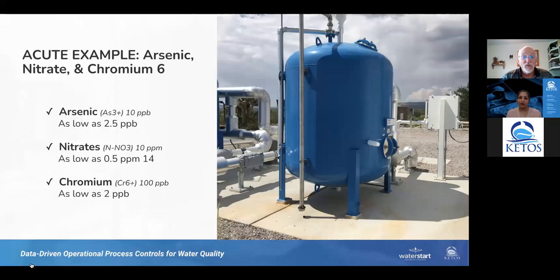In this example, the rule is 10 parts per billion, at least. Some states may have it lower, but the EPA limit is 10 parts per billion. The instrumentation in this example can go as low as 2.5 parts per billion, so they can see it starting to break through, go out there, and change the canister.